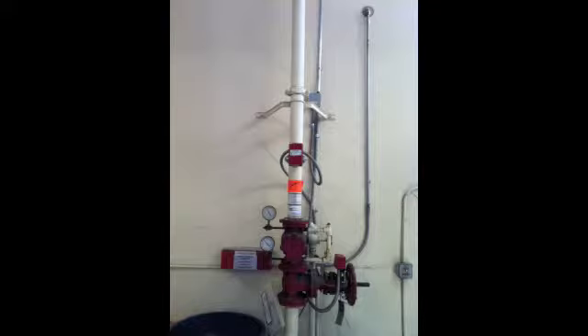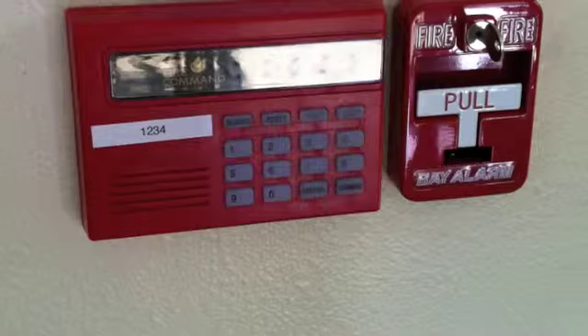The red box highest on the pipe is the VSR water flow switch. The VSR is used as a sectional water flow detector on a large system. The switch is actuated when a flow of 10 gallons per minute occurs downstream. The VSR contains two single-pole double-throw snap-action switches and an adjustable, instantly recycling pneumatic retard. As pressure gauges drop, the water will flow through the pipe, alerting this bell on the outside.